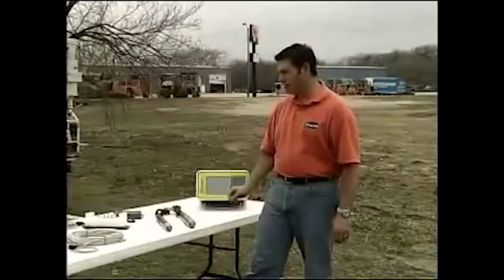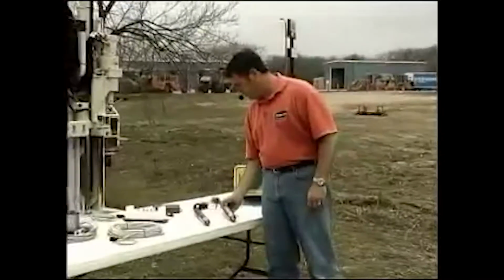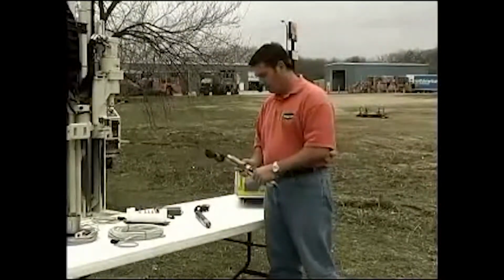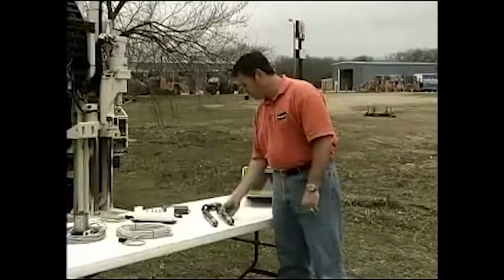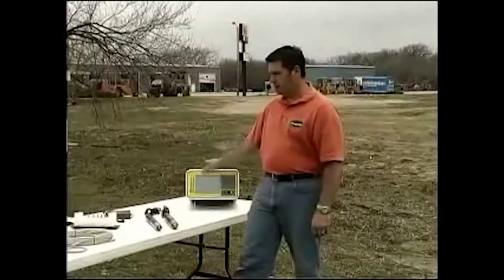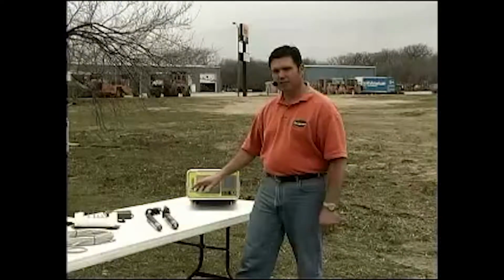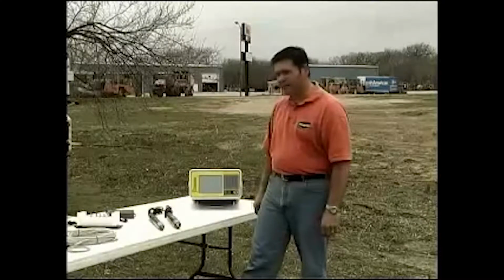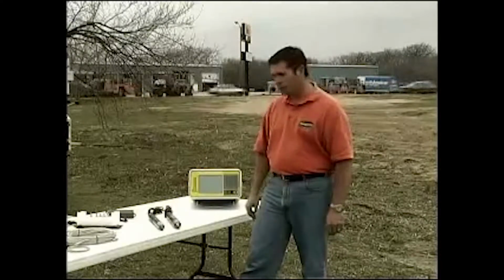Same thing applies as other tools, in that we've got sensors or contact electrodes down hole that receive signal. So ultimately in this system we've got two cords that run to the field instrument, one being depth, one being conductivity. We store those on the computer and they can be downloaded later for viewing or editing.